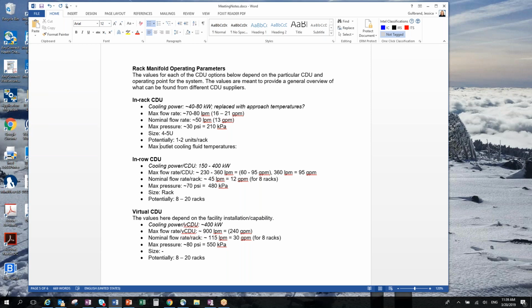All I was getting at is, in my view, the manifold has to be designed with the IT equipment cooling solution in mind, not the data center cooling solution — it's very different. We call out 40 kilowatts or 80 kilowatts, but from an IT design perspective, flow rates and things like that don't necessarily scale with power. It's very different if you're putting a 5 kilowatt 1U node in there versus a 2 kilowatt 1U node. At the end of the day you can still come up with 40 kilowatts at the rack level, but the node level requirements and the manifold design really depend on the IT equipment design.